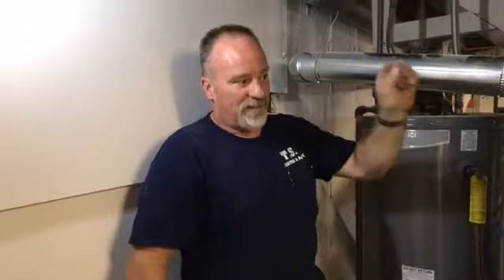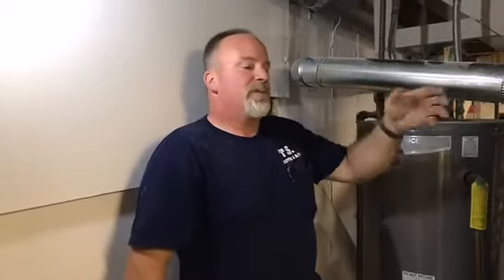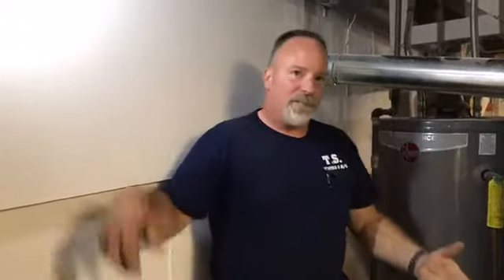And when I see a reading that tells me that there is something leaking, I then have an inspection camera with a 3-foot lead that actually goes up in the heat exchanger, and I can take video and pictures of the inside and see. Okay, so what is a normal level of carbon monoxide? Zero.